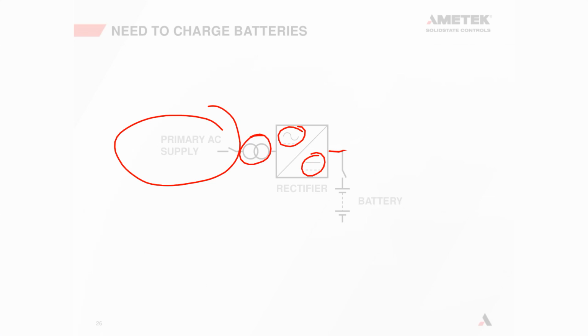And what we do is we take the primary AC supply. On our industrial systems, we go through a transformer, and then we go through a rectifier bridge. And that converts the AC here into DC here. And its sole purpose is to keep the batteries charged at the level that the battery manufacturer stipulates the batteries should be charged at. Okay, a lot of people think that the voltage that the charger rectifier creates is, because we're going to actually add an inverter on the output here in a minute, specifically the voltage that the inverter needs, but it's not. It's got nothing to do with the inverter.